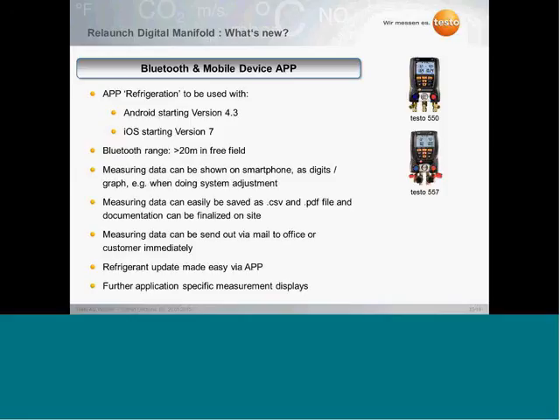And what is also very interesting, you can update your refrigerants on your digital manifolds using the Bluetooth and the app. So if the 6 refrigerants are not enough, or you need a refrigerant which is not listed in the instrument, you can choose one of the 74 refrigerants we are at the moment offering and put it on the instrument. Of course, in the future too, because the world of refrigerants is changing constantly due to emissions, we will update these refrigerant files on your smartphone, like an app is normally updated, and you will be able to put the data on your manifold.